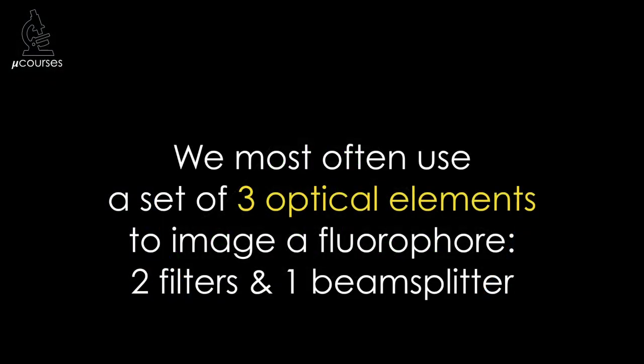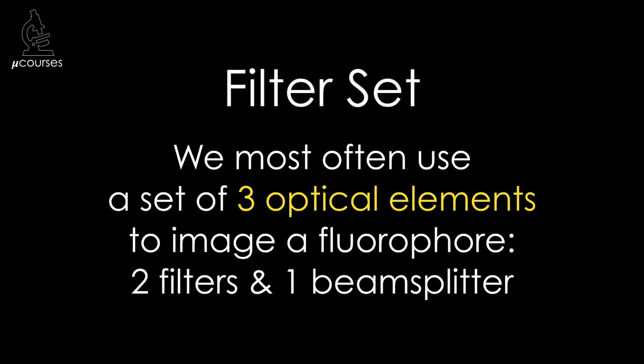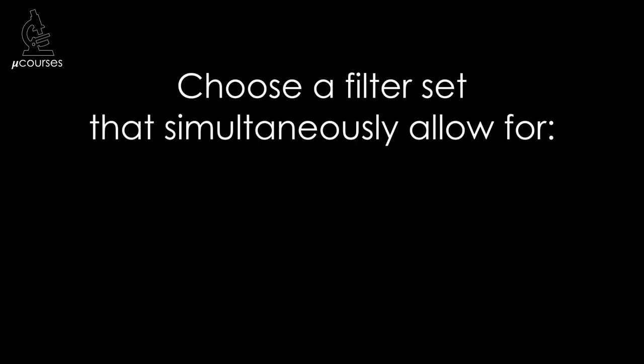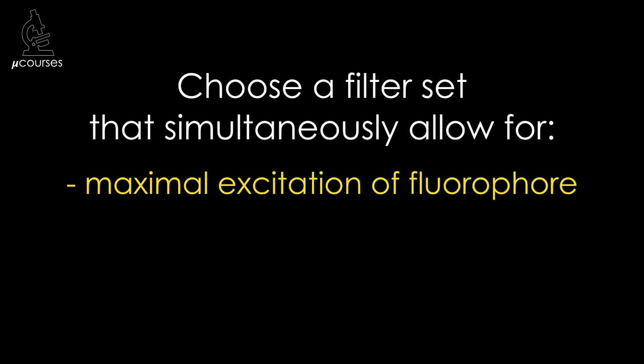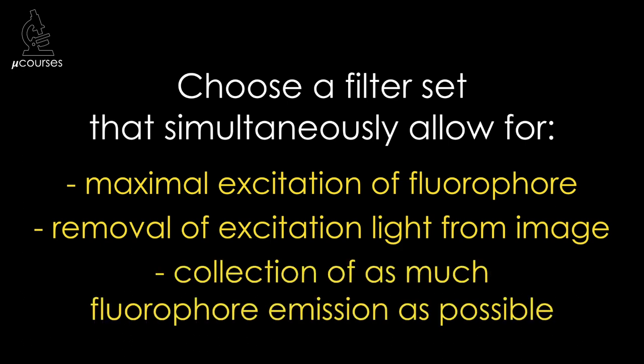To excite a fluorophore and collect the emission light, we most often use a set of three optical elements, which we call the filter set. The filter set is made up of two filters — including the emission filter — and one beam splitter. The optical elements in the filter set should be chosen to simultaneously allow for maximum excitation of the fluorophore, removal of excitation light from the image, and collection of as much fluorophore emission as possible.